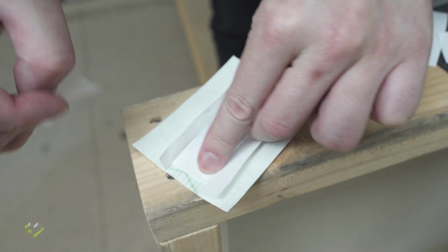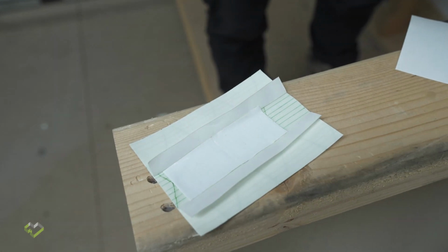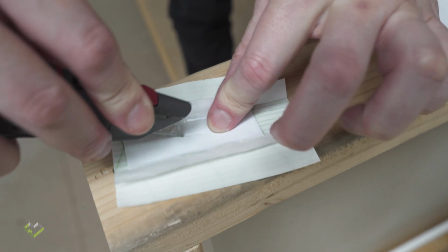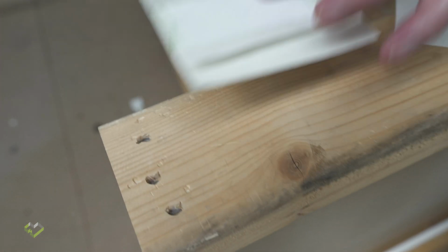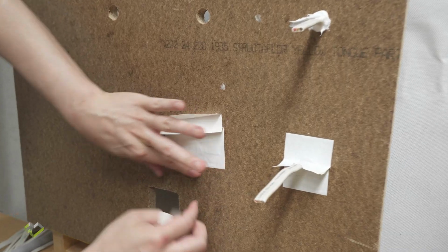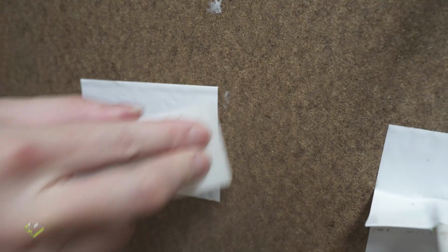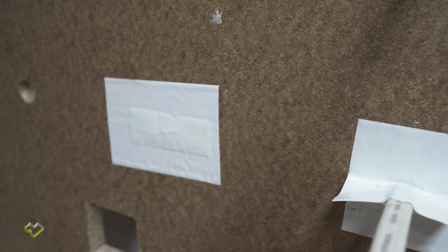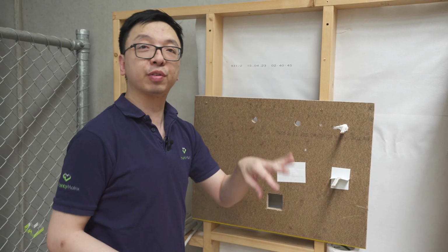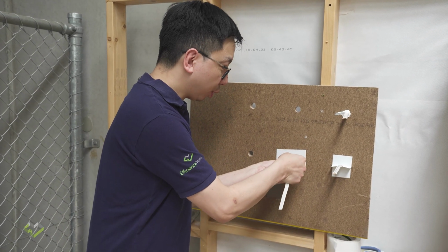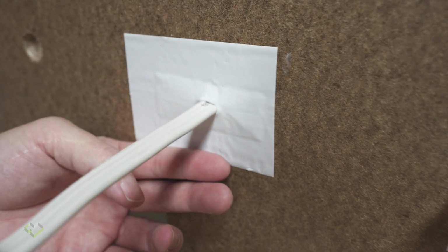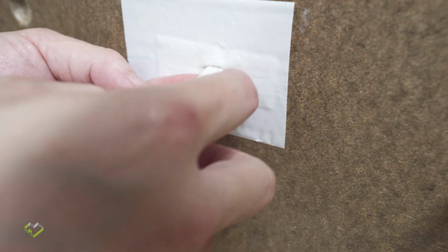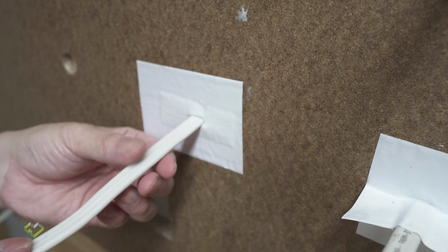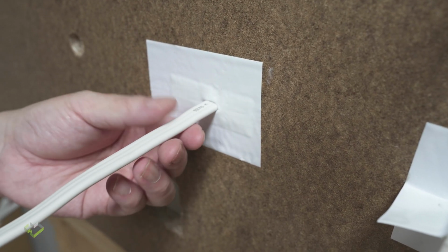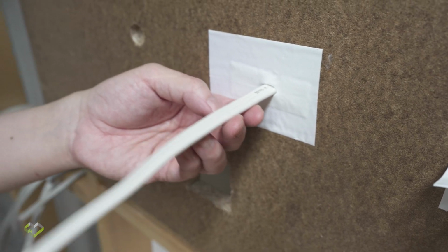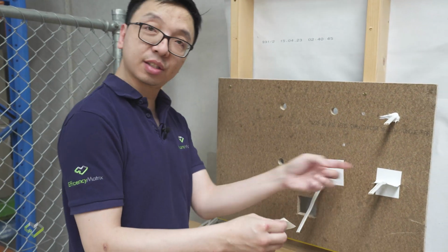After that, we can use a Stanley knife to cut a small hole in the middle, which is similar to the size of the cable. Then we apply this piece to the hole, like normally how we deal with tape. And because I've put on a piece of tape at the back in reverse, now when the cable comes through, the glue is not going to grip on the cable. It creates a reasonable seal, but still allows you to pull the cable until you've got the other end fixed. Then we can come back and tape it as in the second method.